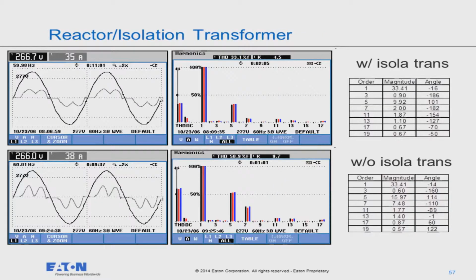Here's an example of using an isolation transformer in front of a drive compared to just having a small reactor inside the drive. Okay? So you see the wave shape here and the wave shape there. This looks more linear, more 60 hertz like, and less harmonic current. So the fifth here is 9.92 amps, fifth here is 15.97 amps, okay? So you're reducing the harmonic current.